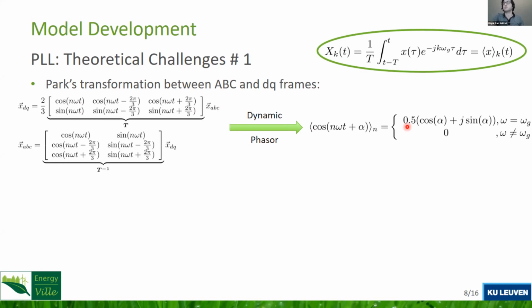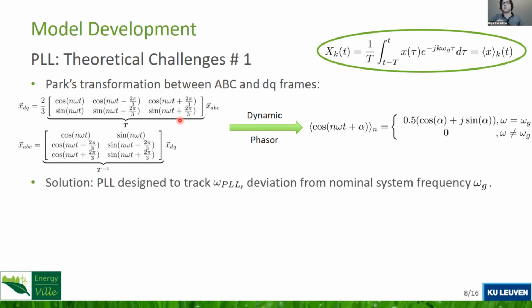However, during disturbances in the system frequency, the components become null, and we cannot calculate any dynamic phasor representation of these matrices. Our solution is to design the PLL to track omega PLL, which represents the deviation from the nominal system frequency omega g. This is actually equivalent to having two different DQ frames: one global DQ frame rotating with omega g, and the other, the converter DQ frame, rotating with omega g plus omega PLL.